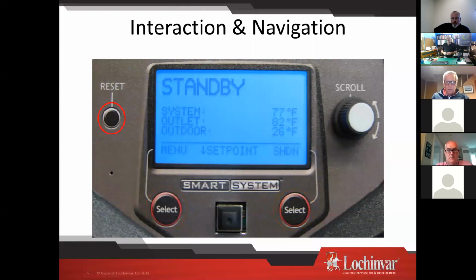Reset: reset the boiler out of a lockout. It's the only thing that does. It doesn't reset a parameter that you programmed or anything like that. It just resets a manual reset. And the service button right there is going to be able to set the boiler into the service mode of firing.